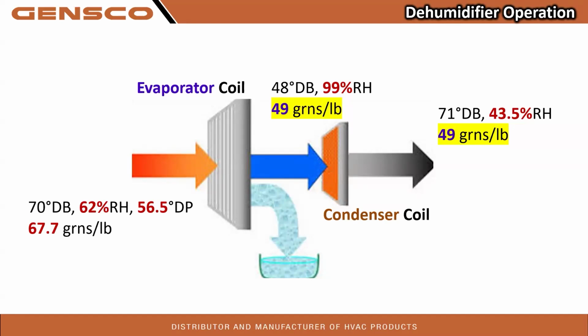A better option for this, and this is money in your pocket if you can identify this up front, or at least raise a possible concern with the homeowner that they may have to look at other means for controlling humidity, is a dehumidifier. A dehumidifier works by taking the air through an evaporator coil, removing physical water, and then reheating it with the condenser coil and bringing it back up to near, or sometimes a little bit less or a little bit more than, the actual room temperature. But we physically can remove water without changing the room temperature. I can't do that with cooling in a system because I'm going to lower the temperature. So you may consider a dehumidifier as a better option if you run into humidity problems.